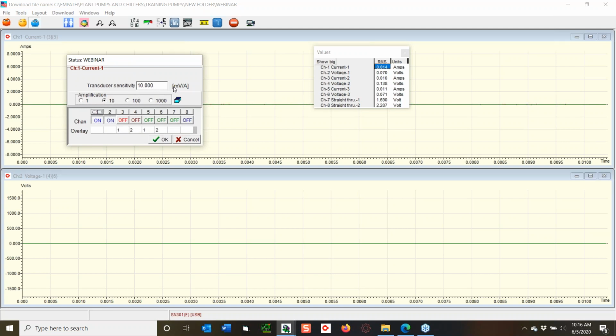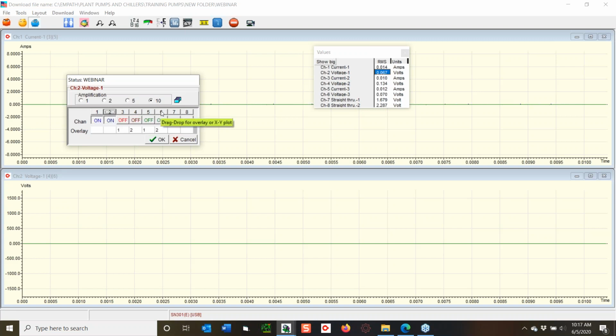10 millivolts per amp is default, but if you have a BNC current clamp of any type, you just put the conversion rate in here on each channel. So for this it'd be 1, 3, and 5. 2 is voltage, so that's going to be different - 2, 4, and 6 is voltage. So 10 millivolts per amp means whatever I've connected up will do that.